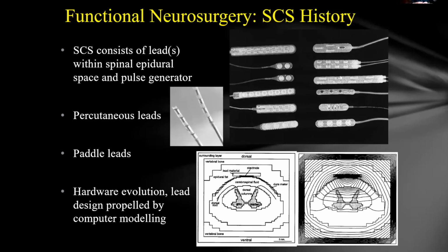As you can see, those percutaneous leads in that box in the middle have 4 contacts on them that are cylindrical with contact all the way around. If you look on the right to the paddle leads, it's hard to tell a little bit, but they have a lot of different electrode combinations and orientations. But the most important thing is they're insulated in the back with a plastic covering.